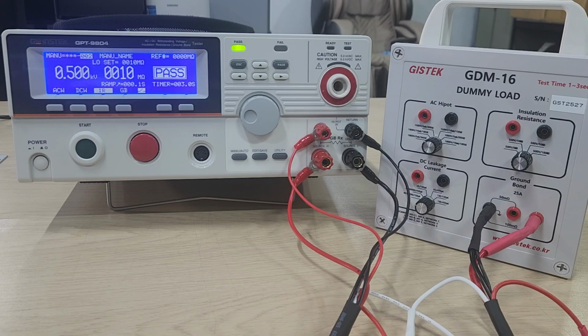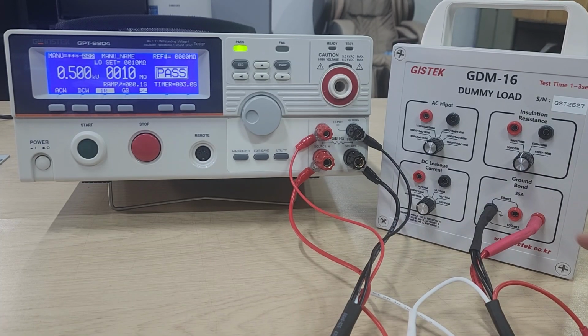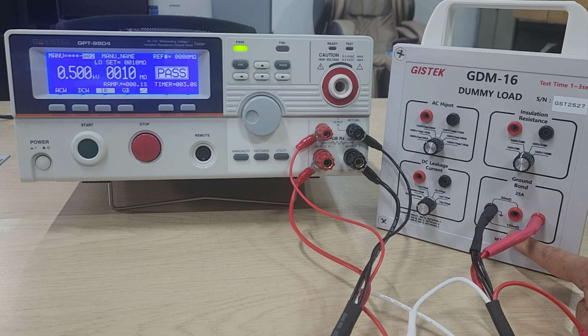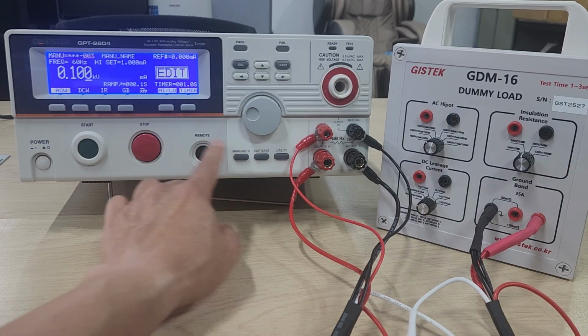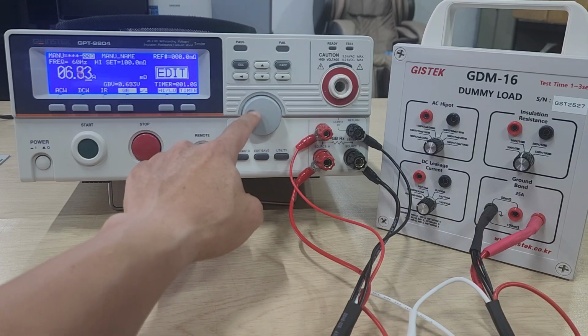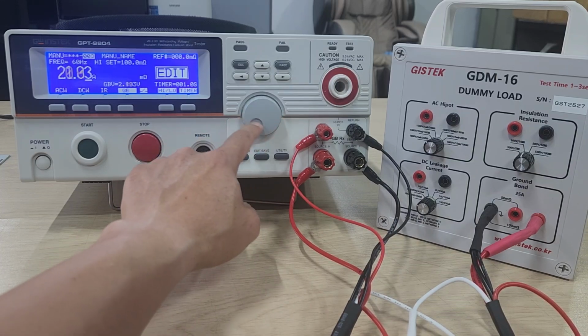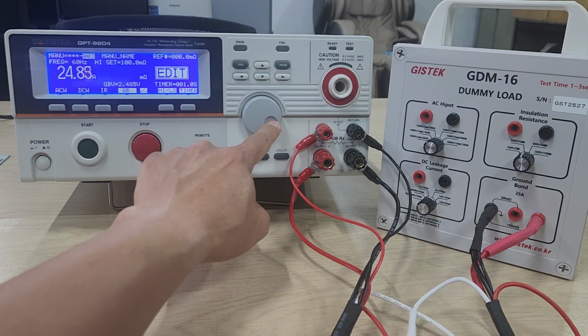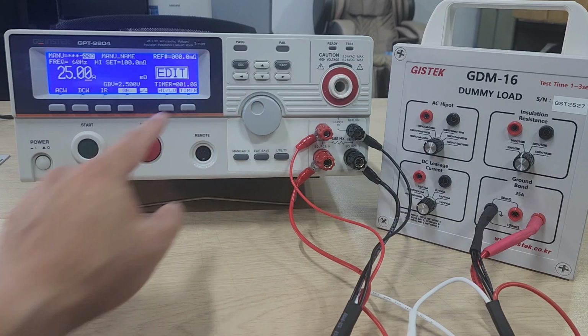Select the AC ground resistance test channel from the dummy load. I select the 100 milliohm channel. And next, set the test condition on the AC ground resistance tester to 25 ampere, 100 milliohm, 3 seconds, the same as the condition selected for the dummy load. 25 ampere, 100 milliohm, and test time is 3 seconds.